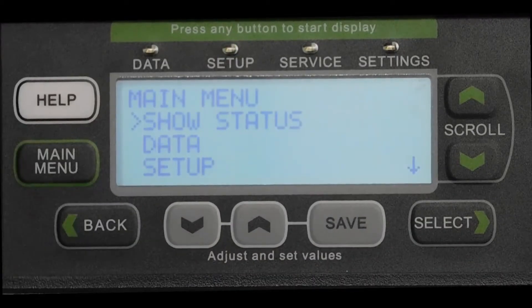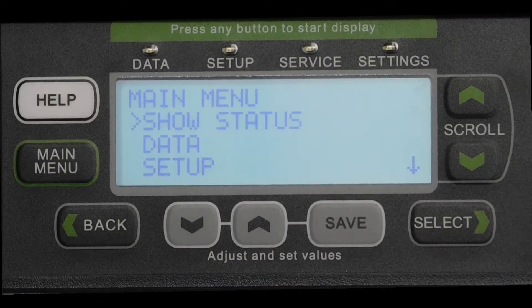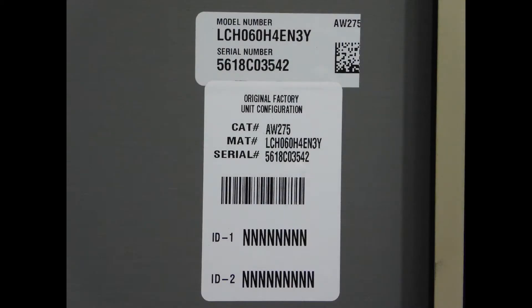For reference, this information can be found on a sticker located on the inside panel. Pay special attention to the Configuration IDs 1 and 2, as they may need to be adjusted if an accessory was installed in the field, such as electric heat or an economizer.